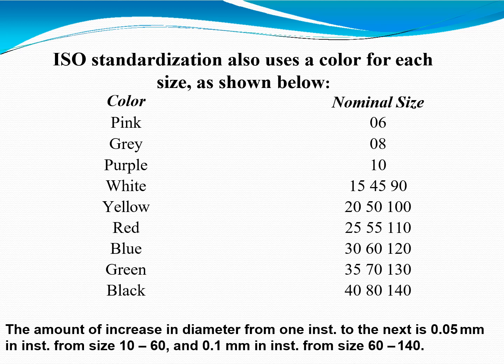ISO standardization also uses a color code for each size: pink 06, gray 08, purple 10, white 15/45/90, yellow 20/50/100, red 25/55/110, blue 30/60/120, green 35/70/130, black 40/80/140. The increase in diameter from one instrument to the next is 0.05 mm for instruments from size 10 to 60, and 0.1 mm for instruments from size 60 to 140.